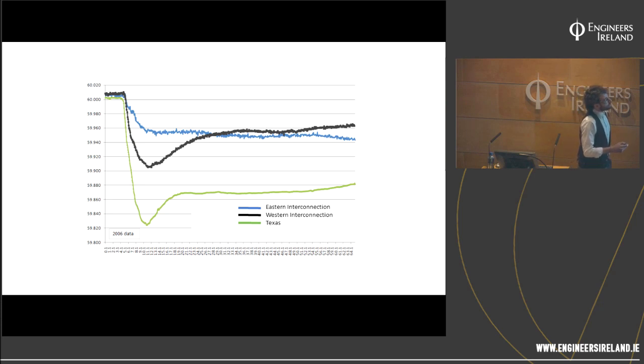Now, these rates of change, that initial slope, that's what the inertia governs. These different characteristics along here are different response time frames. When I'm talking about the inertial time frame, I'm talking about between 0 and 3 seconds following a disturbance on the grid. This will run out for up to minutes, and these characteristics are different. For example, in the Eastern interconnection, a lot of generators lock their governors. They lock the control because they're not mandated or paid or incentivized to have that control. And that's why you get that lazy L shape on the Eastern interconnection, even though it has heavier inertia. So I suppose there you can see already that economics is driving the technical response of a power system.